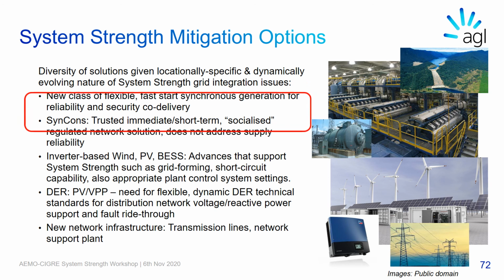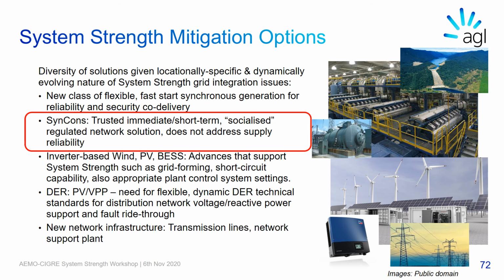Synchronous condensers, or syncons, provide a tried and trusted solution that has been well demonstrated in other jurisdictions, such as in Europe, to support higher levels of renewable energy integration. It represents a socialized, regulated network solution approach to ensure diversity of system strength solutions. Of course, we should note that syncons do not provide megawatts and therefore do not address supply reliability requirements.